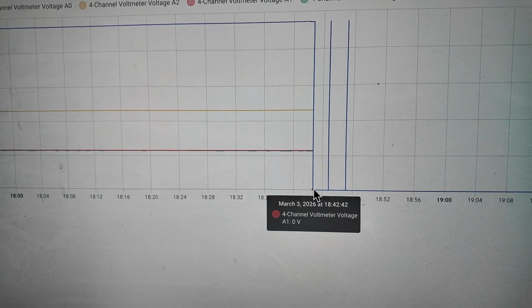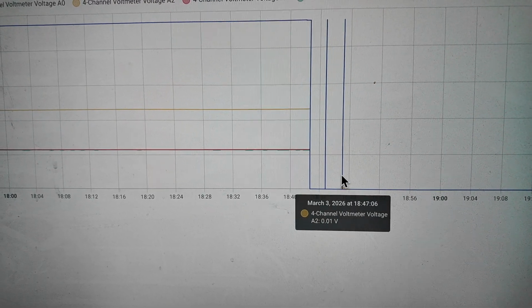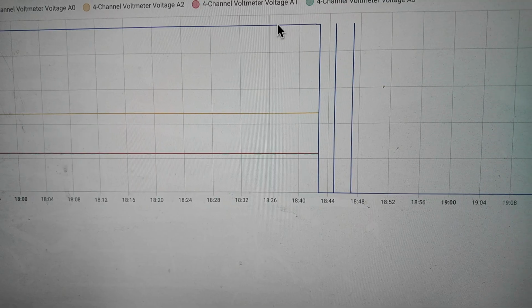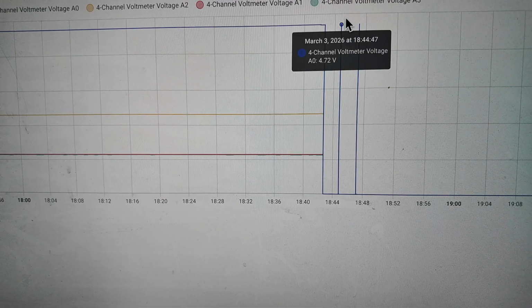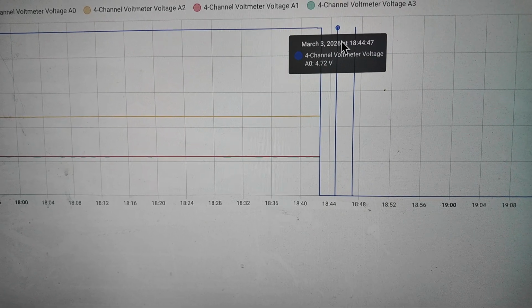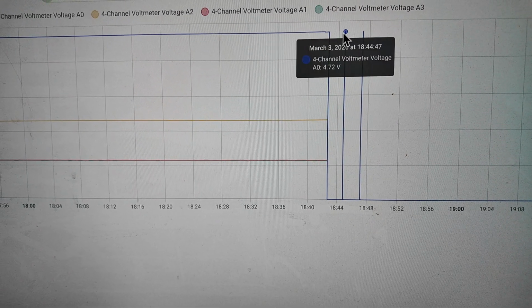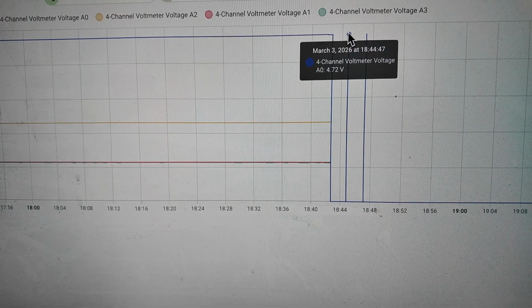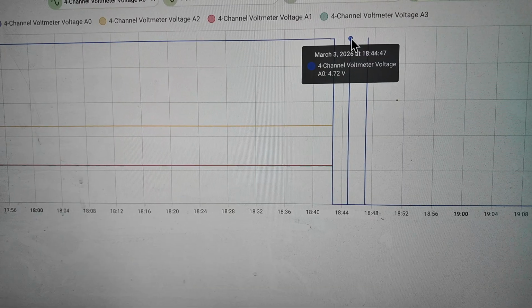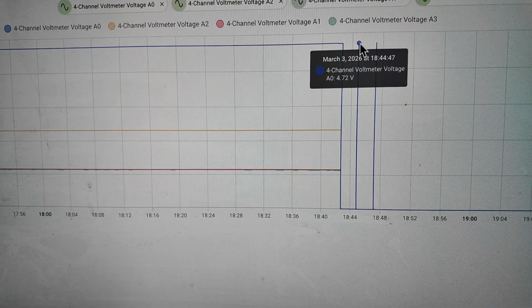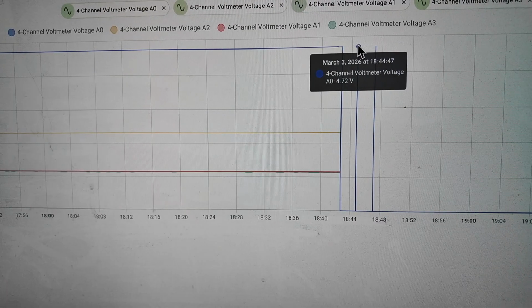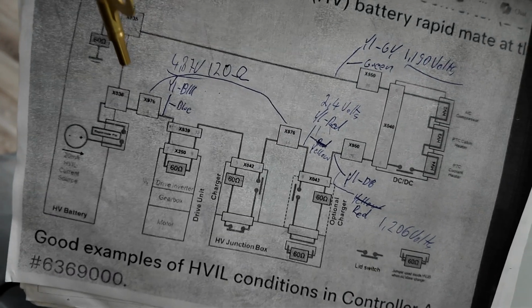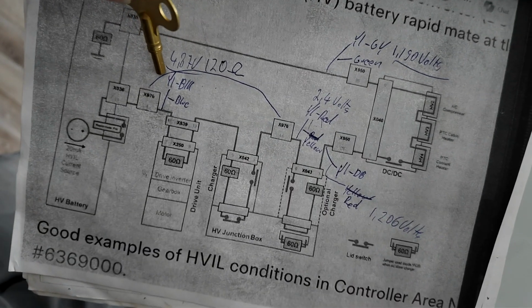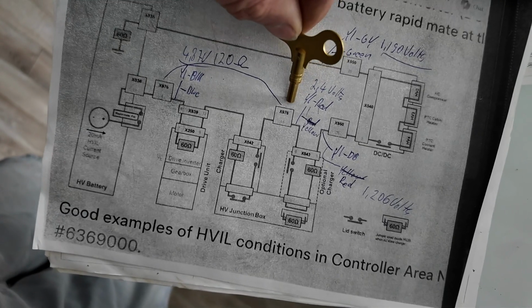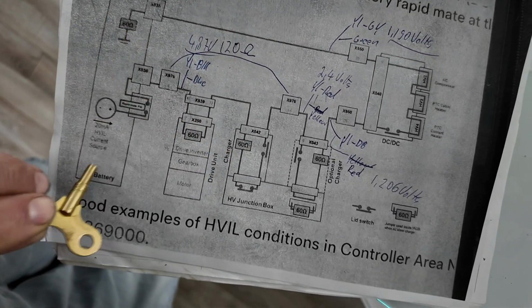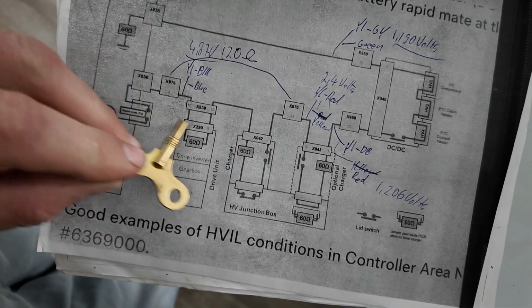And then we still had some signals going up from, this is the blue cable connected, basically coming right out of the battery pack. At the beginning I was quite hopeful that I already isolated the problem, because to me it looked like there was an interruption right after here. That would indicate it would be between here and the charger. So we were getting the signal right here, coming out of the battery, but not on this end, so after the drive unit and the charger. My first impulse was that we have an issue right in between here.